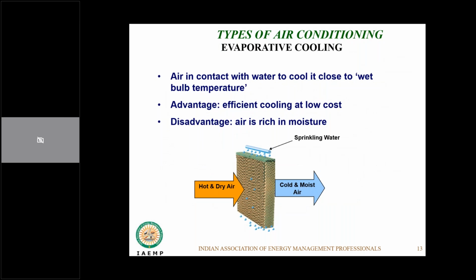Moving towards evaporative cooling, I think we all know this. I will just briefly touch on it. It's a simple strategy used in a dry and hot environment, basically where your dry bulb temperatures are very high and your wet bulb temperatures are very low. So the moisture content in the air is very low, and you pass it through a pad over which water is sprayed; most of these are counter flow or cross flow heat exchangers. The air absorbs the water, and by an adiabatic process, it increases its moisture level and reduces its dry bulb temperature. So the air coming out of this pad is relatively cold and moist.